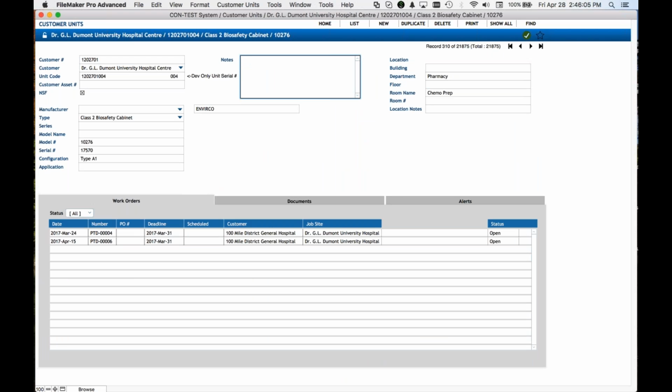Okay. Because I think that's what you want. Because some of our cabinets, for example, there's not enough room from the ceiling to the top of the hood, and the technicians kind of need to know that before they go on site. Excellent. That's the kind of thing that I think should sit in here. Like any testing protocols, or as David said, if the cabinet is kind of acting up this year, but not enough for us to repair it, but maybe by next year, it's good for the next technician to see that same note.